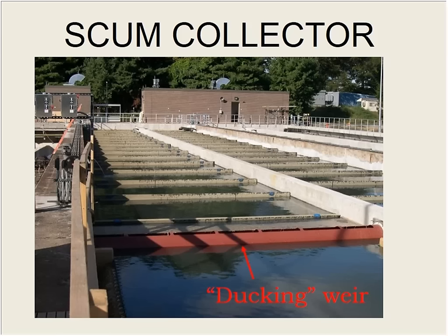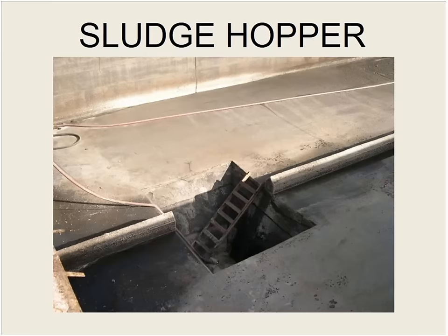On a timer, you can see the openings cut into the top of the pipe. That pipe is going to rotate towards the inlet side, so it goes just below the water. That floatable material will flow into that pipe and then go away to a receiving tank. We've got nice, clean water on this side of it. On the floor, sludge is being pushed back, and that's generally the case. Sludge is generally pushed back towards the influent end of the tank. It's pushed down into this sump, and then it gets pumped into the solids handling unit.